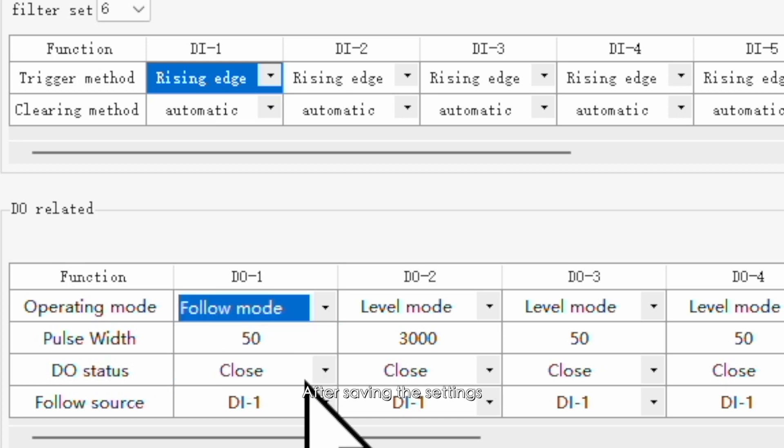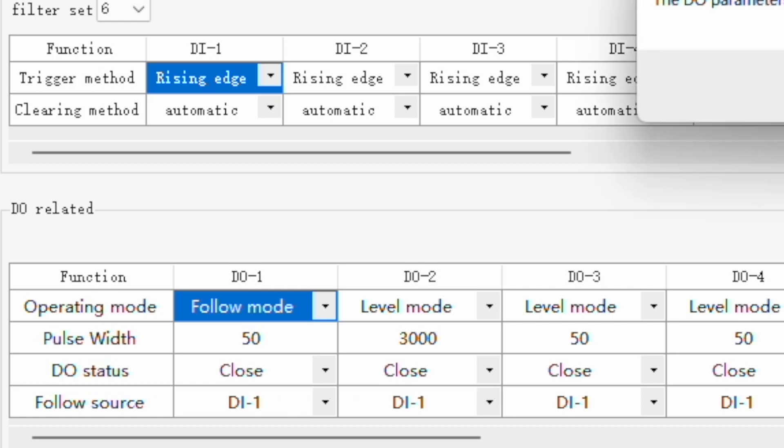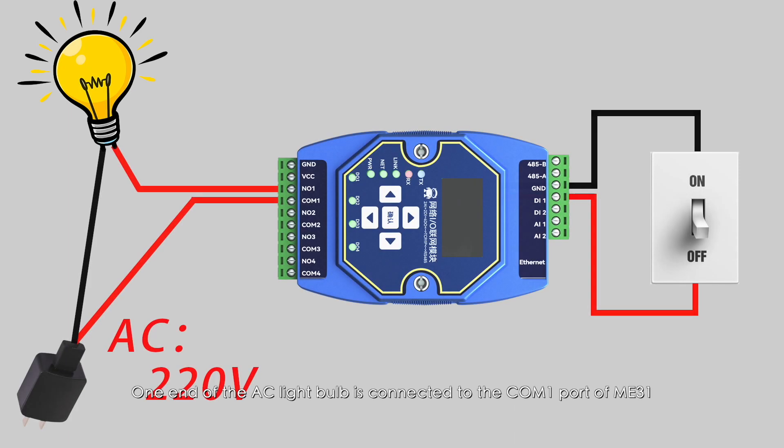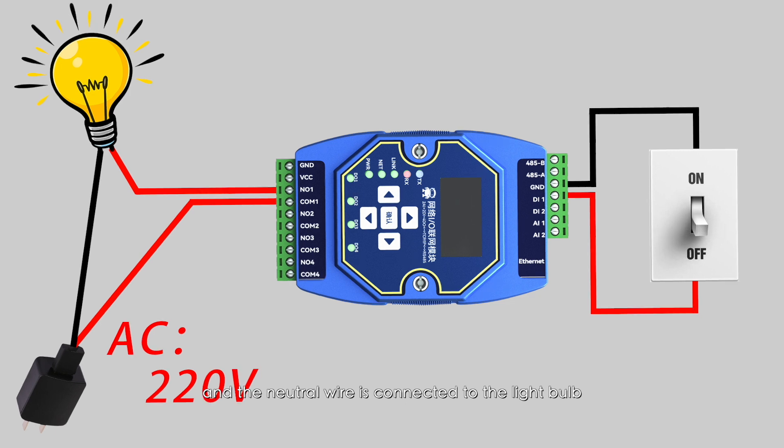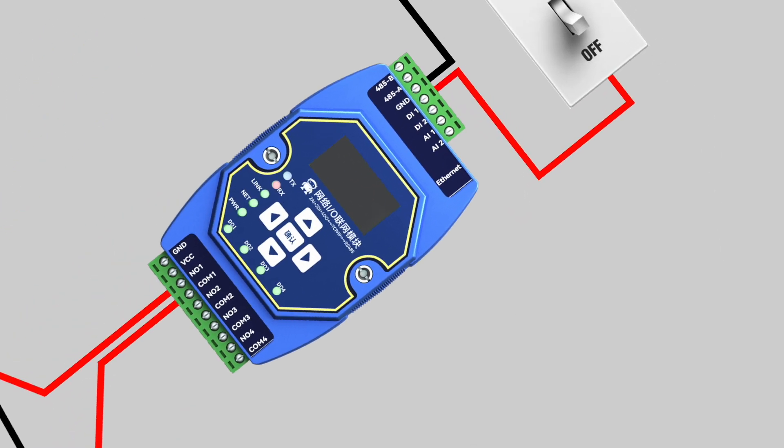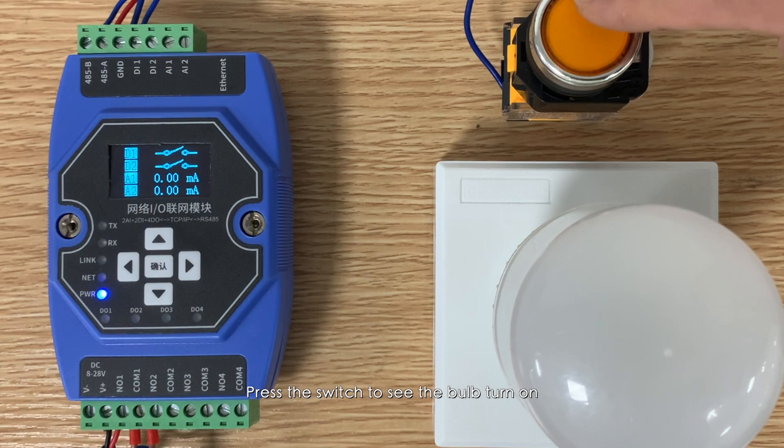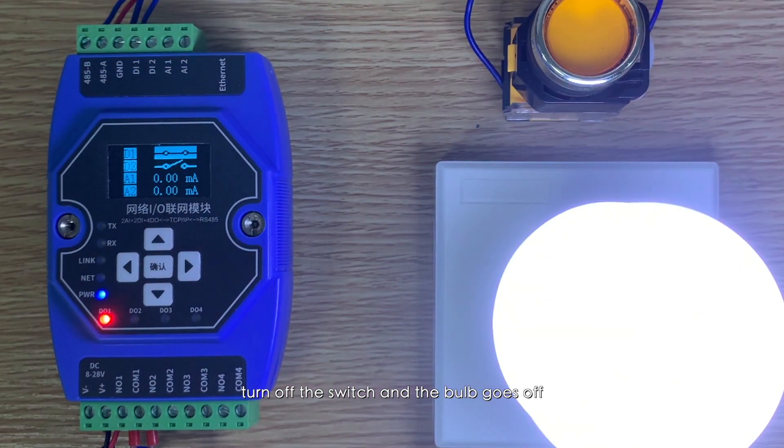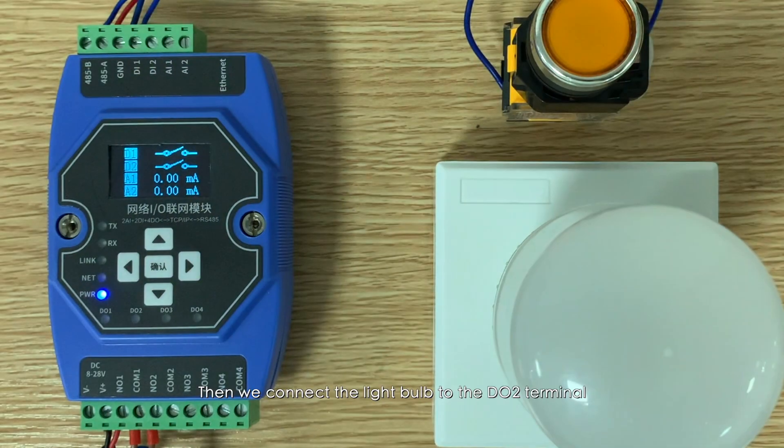Change the working mode to follow mode. We use an AC light bulb to simulate actual usage. One end of the AC light bulb is connected to the COM1 port of ME31, the AC live wire is connected to the NO1 port of ME31, and the neutral wire is connected to the light bulb. Press the switch to see the bulb turn on. Turn off the switch and the bulb goes off.